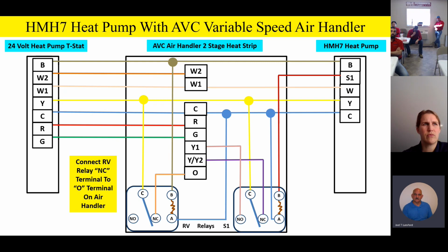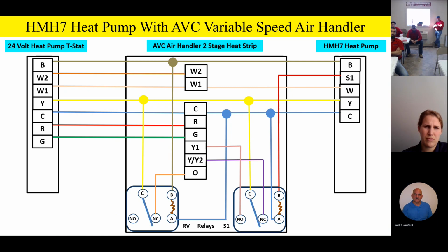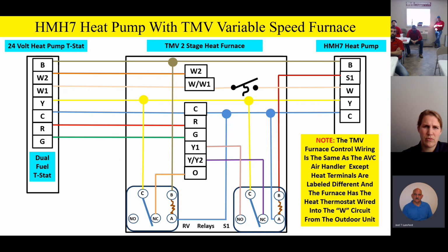Now, let me go ahead and talk a little bit about the variable speed furnace, how it wires, and then we're going to do some animations for you so you can see how all this works for switching airflow and switching the RV relay. So watch this for another minute or two. On the TMV variable speed furnace, everything stays exactly the same, except the terminals. You'll notice that the WW1 terminals are configured a little bit differently, and we've got that little construction thermostat in there to break that W circuit if you have a variable speed furnace in a dual fuel application.